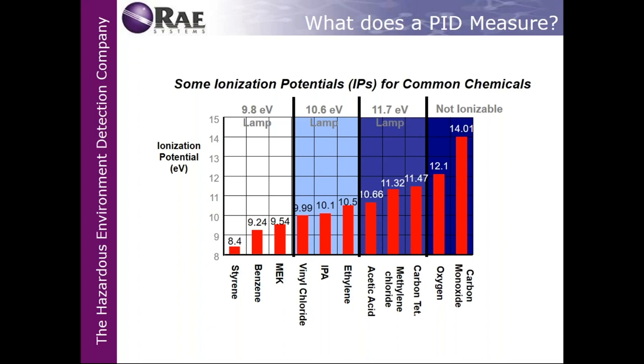Now the thing about 11.7, this is a tricky one, because 11.7 lamps only have a 30-day warranty. Why? That's because the crystal, or the flat part of the lamp, is not sonically welded like the 10.6 or the 9.8. It's actually glued. So there's gas inside the lamps, which in this case would be argon gas. The worst thing that can happen to a PID is probably high humidity or high temperatures that can affect the lamp and microscopically warp it. If it warps that top of the lamp, it'll break the seal and the lamp will burn out.